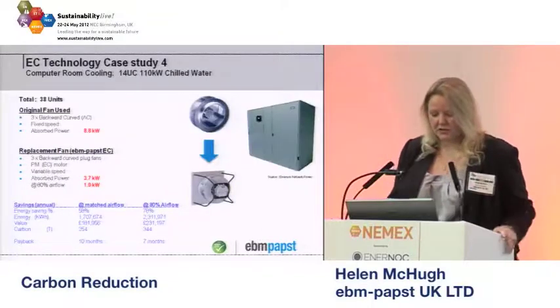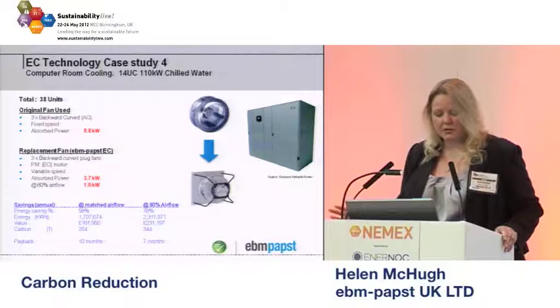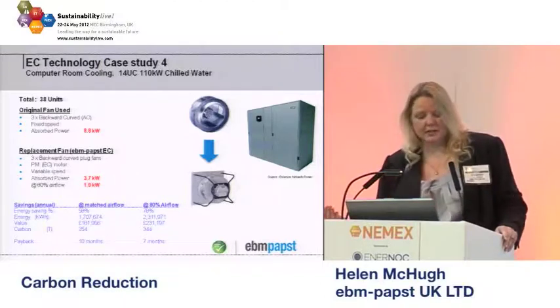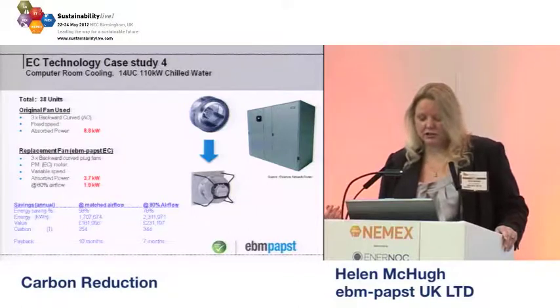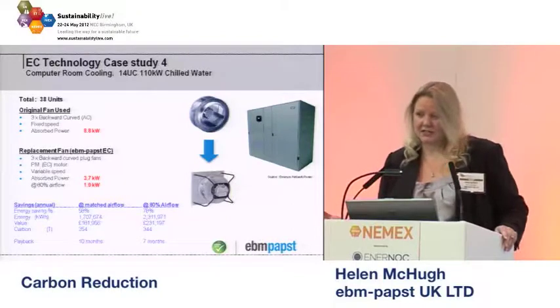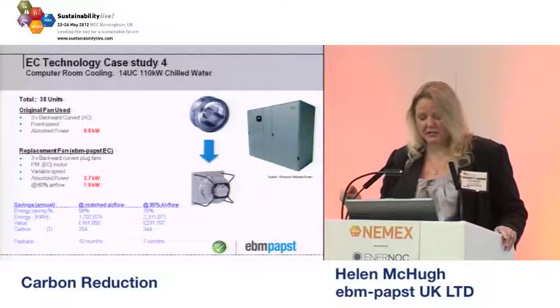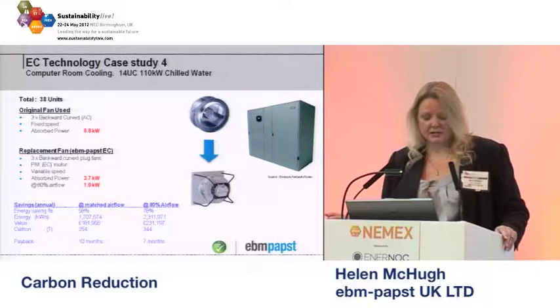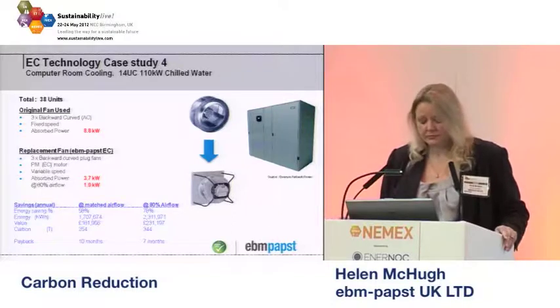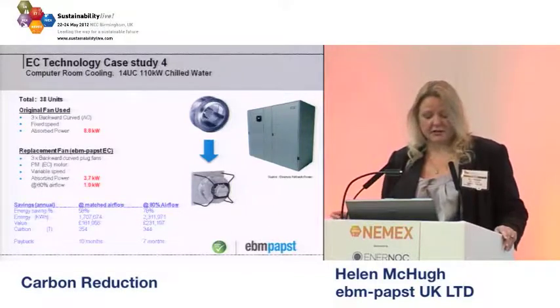And then just to finish off, looking at some computer room cooling. So similarly, we're changing away from an existing AC fan to EC. And here, in this example, we're looking at between 58 and 78% saving. And that really depends, again, on controllability. So for like performance, 58% reduction. And a payback there of about 10 months again.